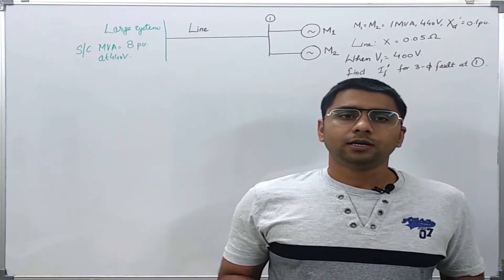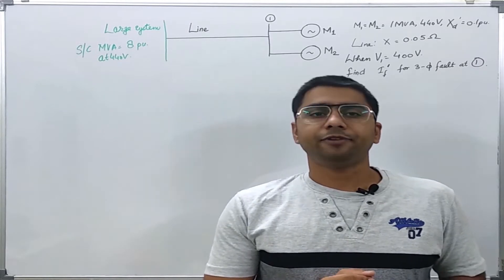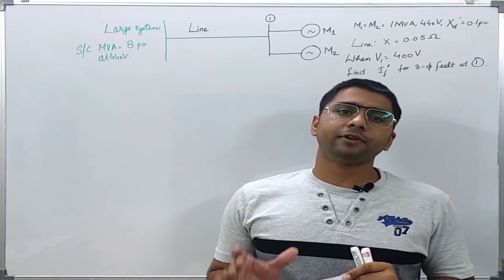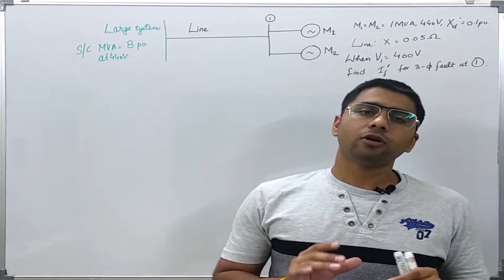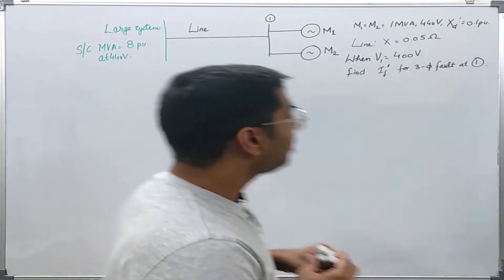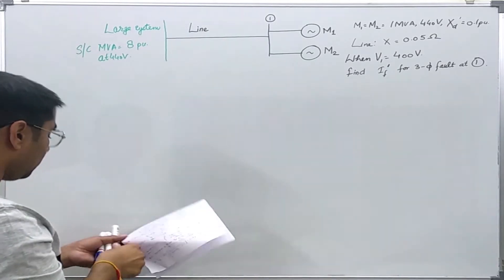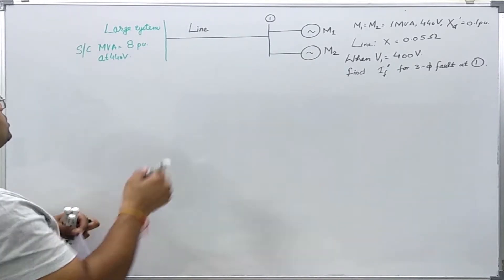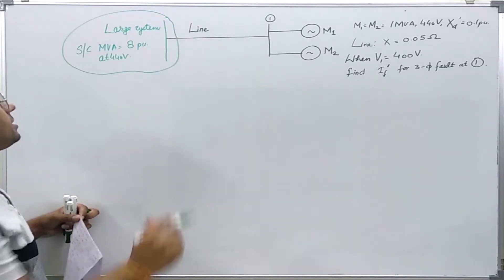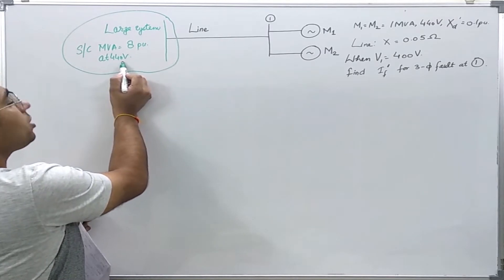Let us see a numerical example which includes the concept of short circuit MVA. This example will show us that the short circuit MVA concept is very useful in fault calculation. We are given that there is a very large power system having a short circuit MVA of 8 per unit at a 440 volt base.